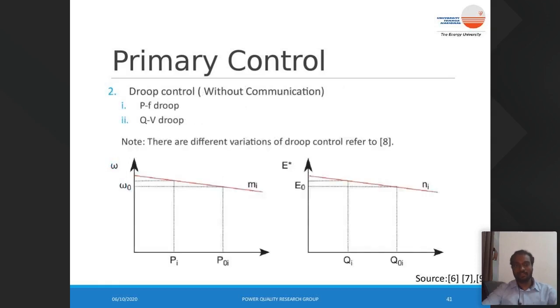Then we have decentralized control, which is a simple droop control. This droop control is adapted from our normal thermal or hydro generation plants, where we use the power frequency droop and voltage reactive power relation. For example, I'll explain with the power frequency droop. Suppose the system is operating at omega naught, and due to a sudden loss of load, the frequency increases to omega 1. Sorry, it's not shown in the figure. Say it increases to omega 1. The controller has to ensure that the power is reduced to P1, so as to restore the frequency to omega naught.